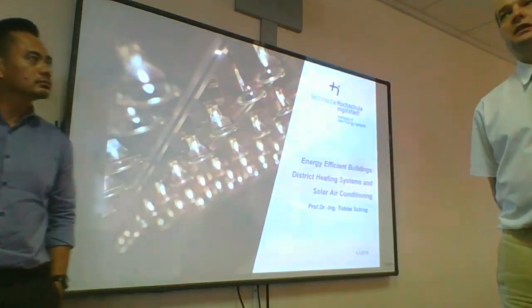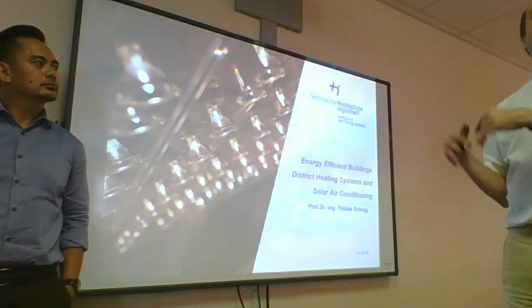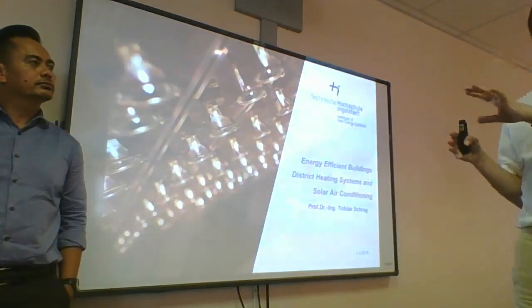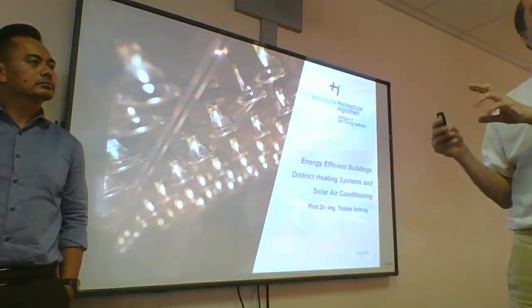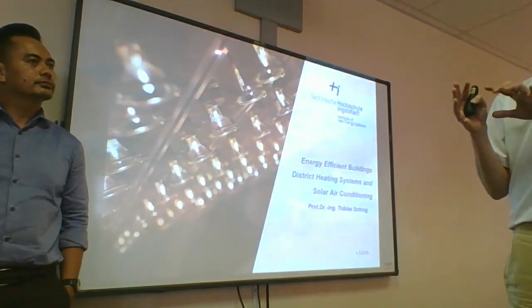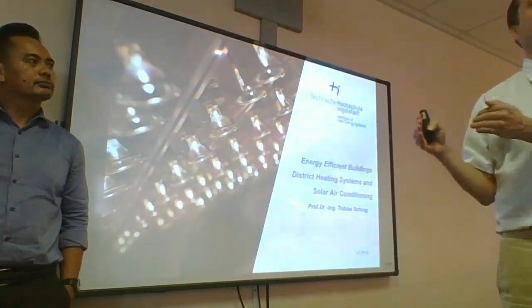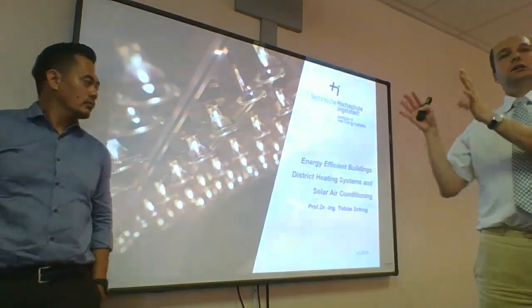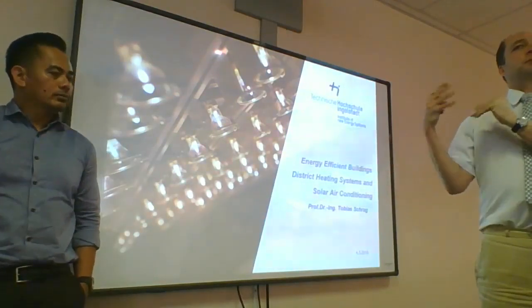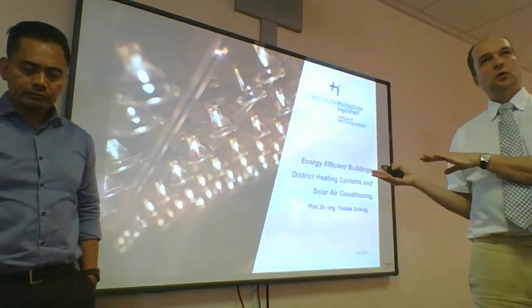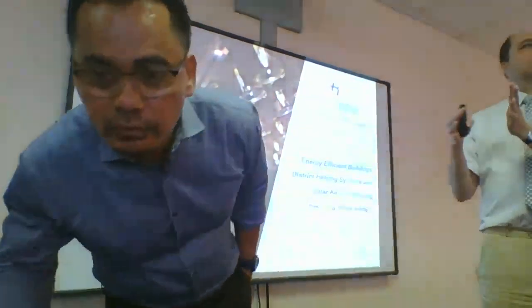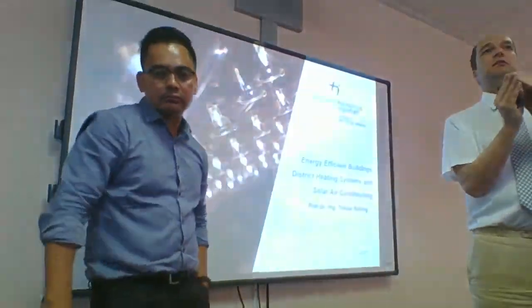In this research project, the controller type was not specified yet. We worked together with a company building a controller, figuring out what should be the logic of the controller, taking into account that the solar system will produce hot water, which can be stored in a hot water storage but not further. The PV system can also produce hot water via a heat pump.